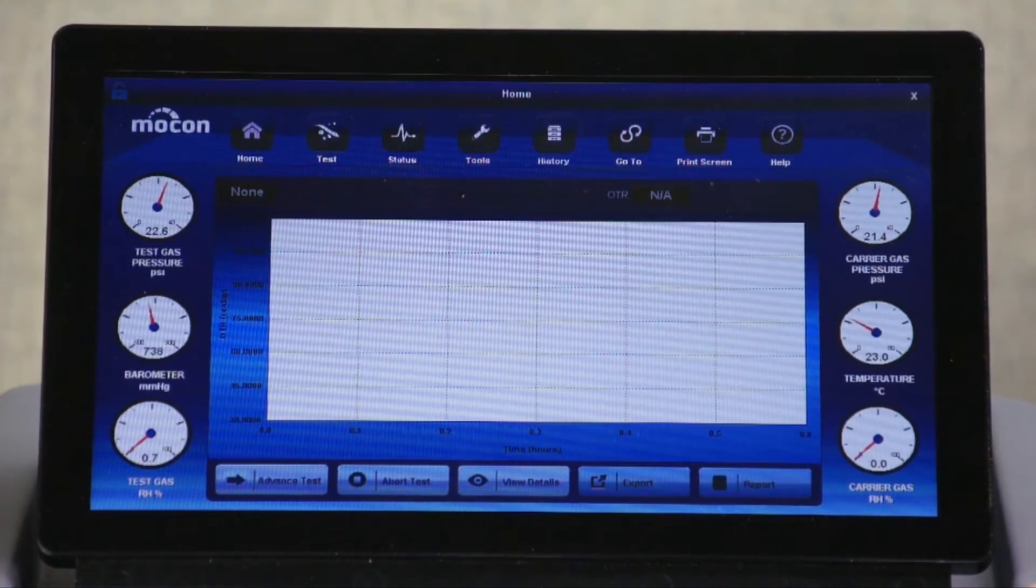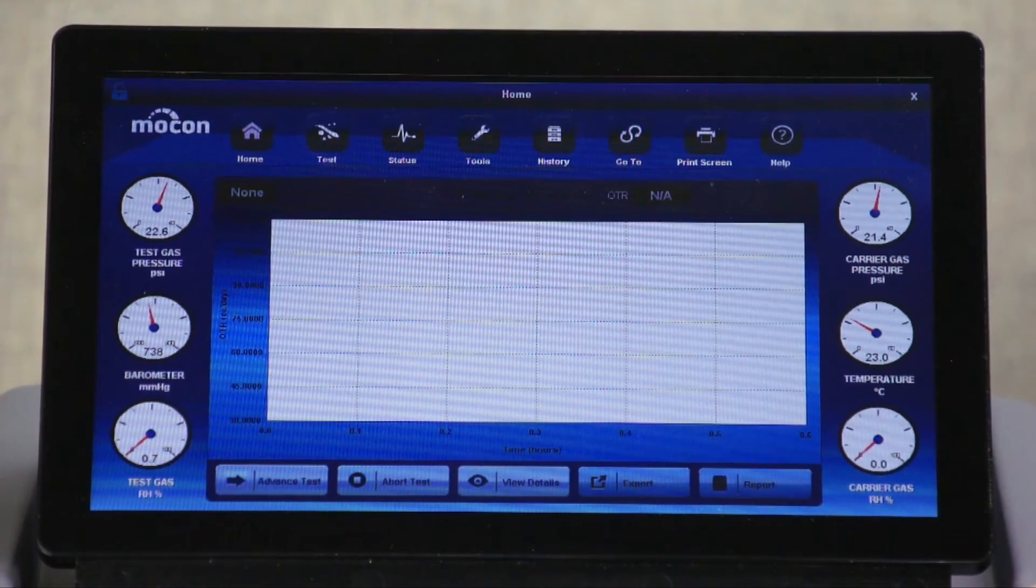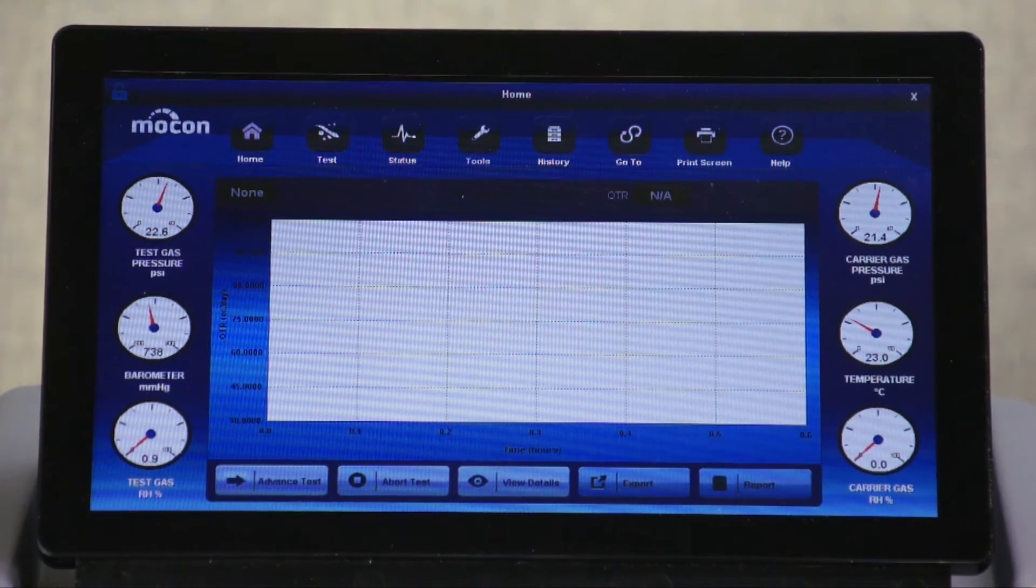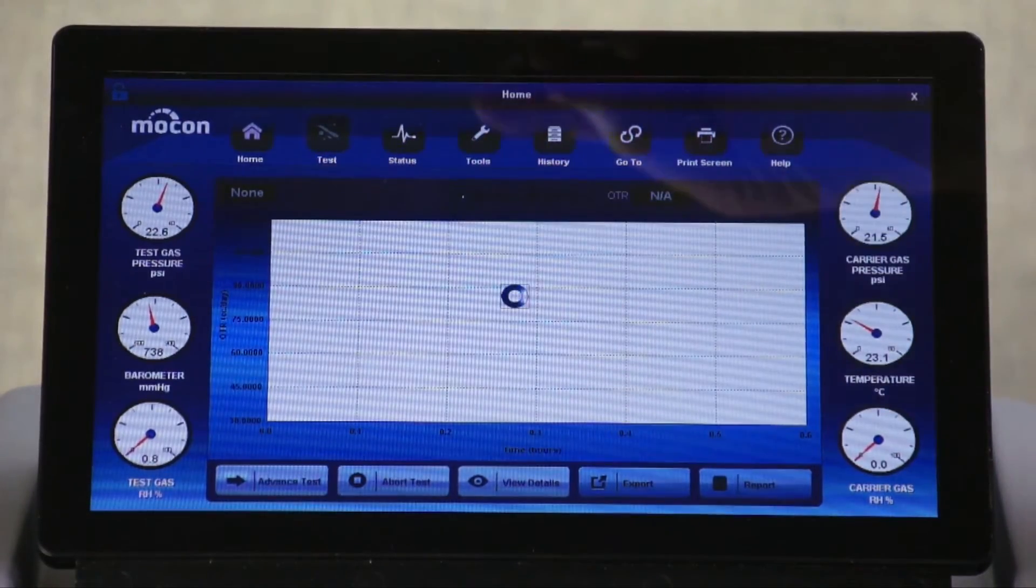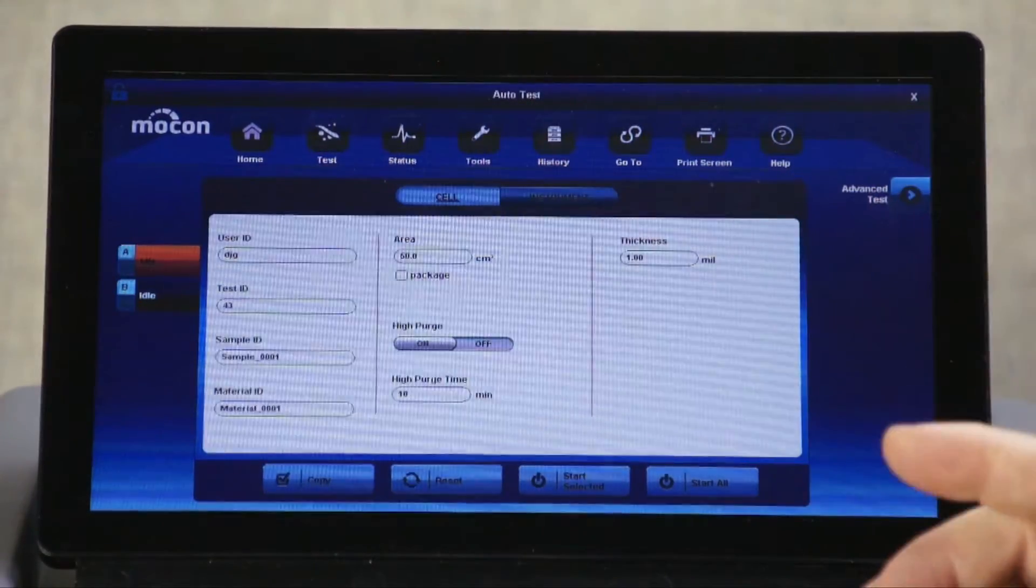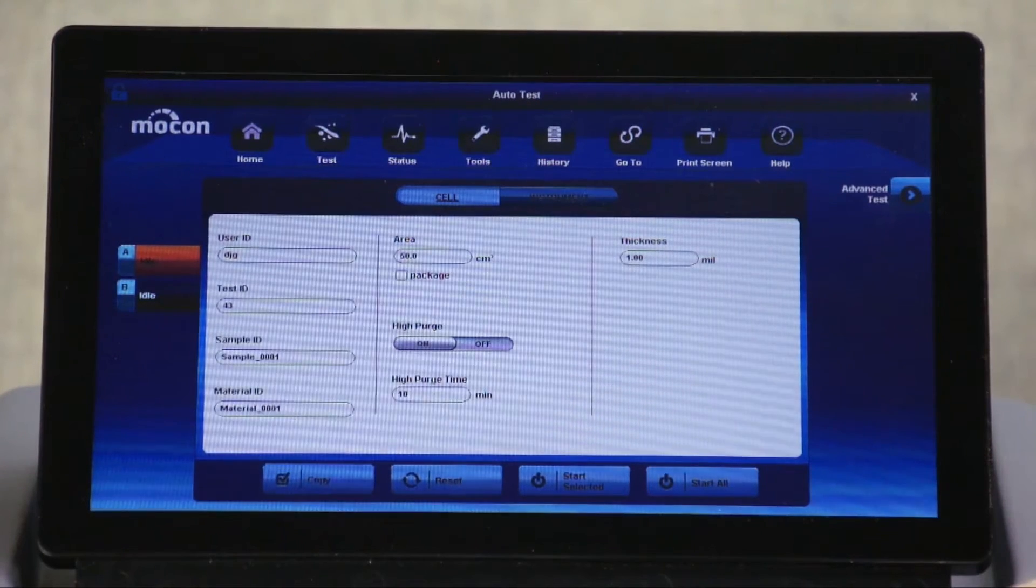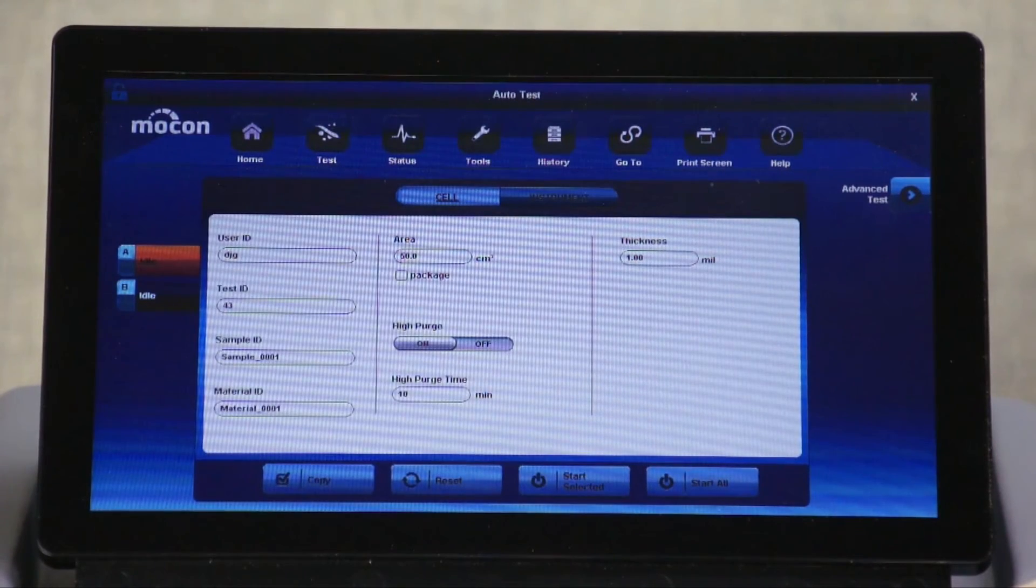The OXTRAN model 222H offers a range of test modes. To start the fully automatic test mode, press test. This mode is simple to use and is easy for a new user or for a protocol that doesn't need the advanced settings.